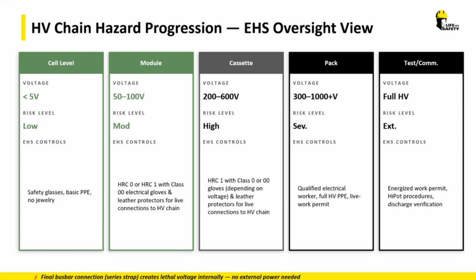The one about test and commissioning - sometimes packs come back, right? We get returns, or they've kicked off a line for some reason it didn't meet whatever standard, and it goes to a rework station. And I will tell you that from my experience, those reworks coming in from the field as a rehab, or a device taken off the line because it failed some part of the quality program, that's usually when we tend to have failures.